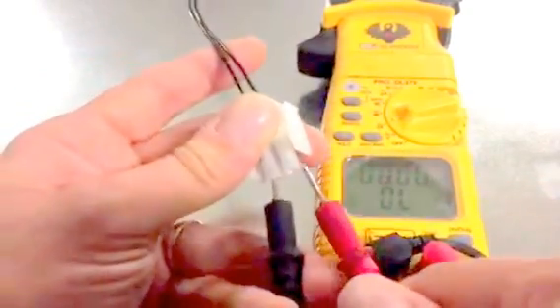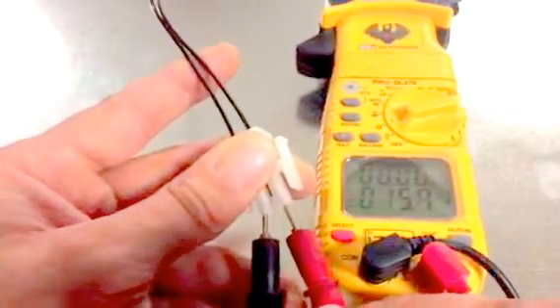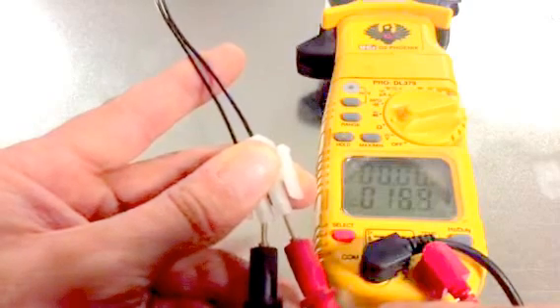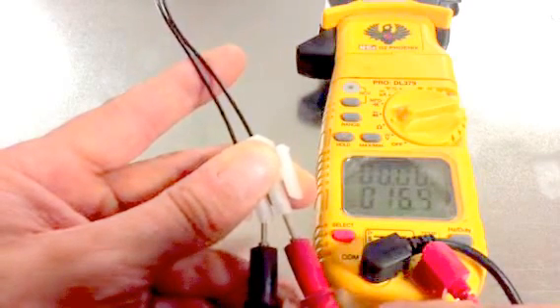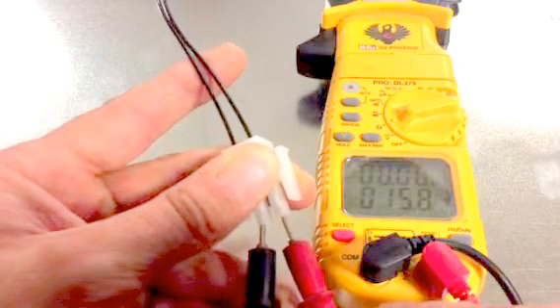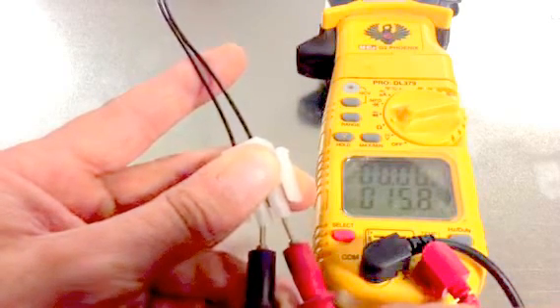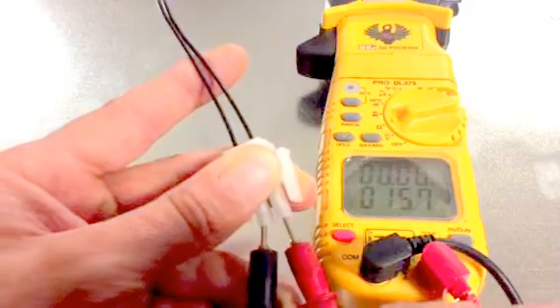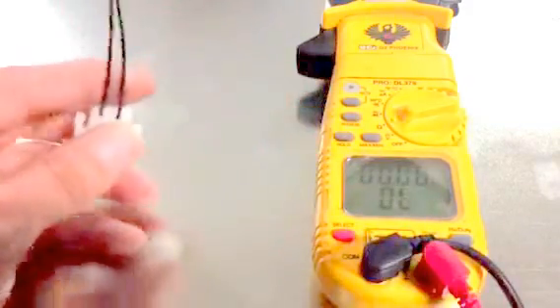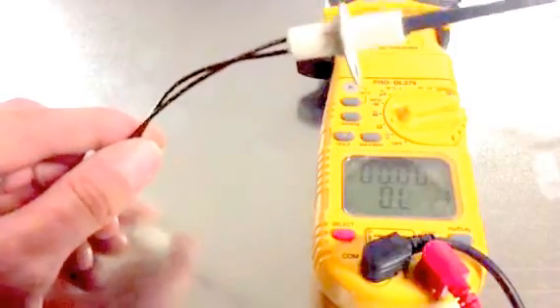Like that, you can see we're reading 15.7. Let it stabilize here. I think I lost connection there for a second. Okay, 15.8, where we're kind of stabilized there close to it. Now these should read somewhere between 11 to 18 ohms new.